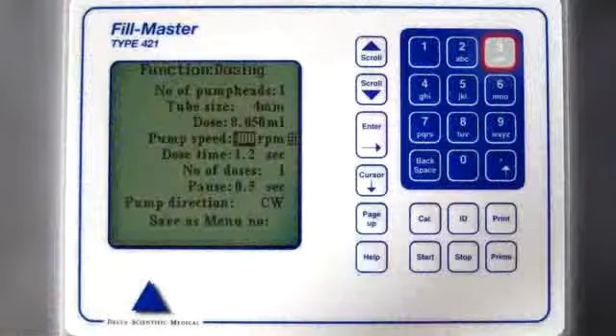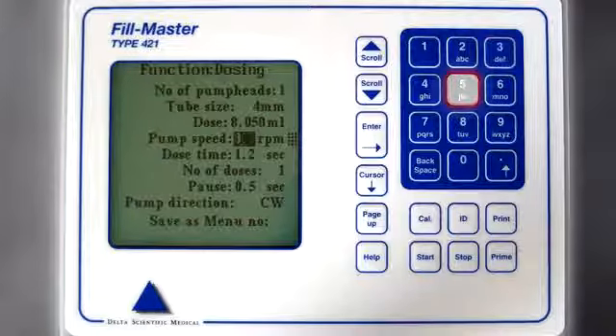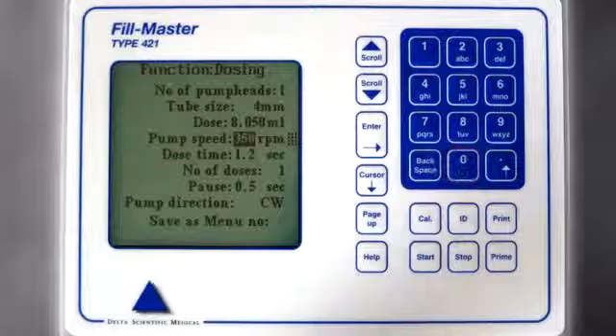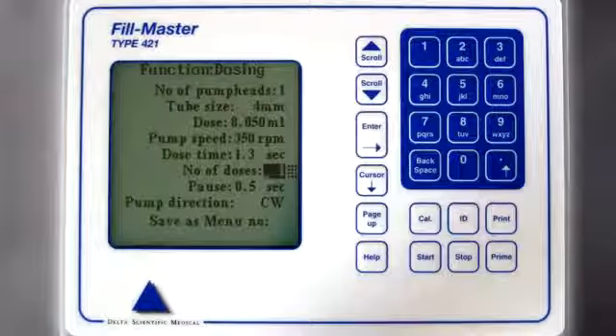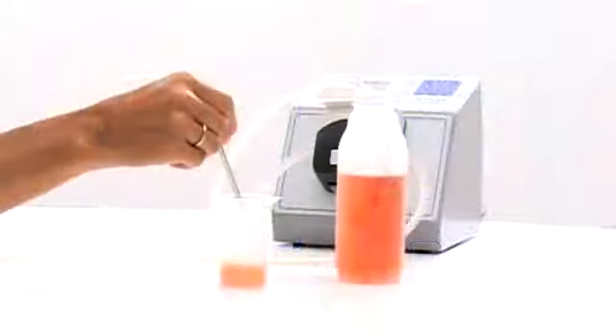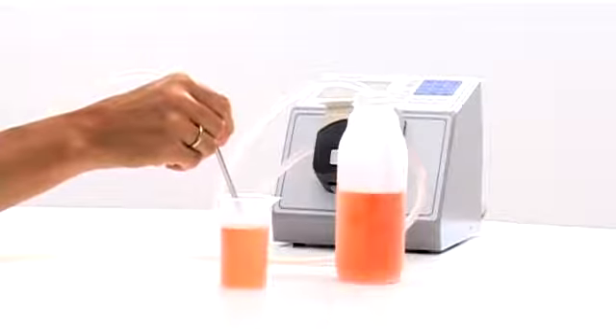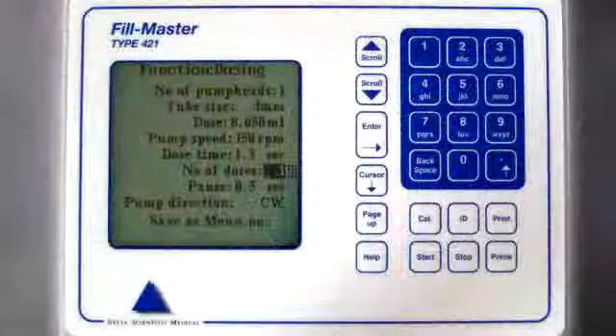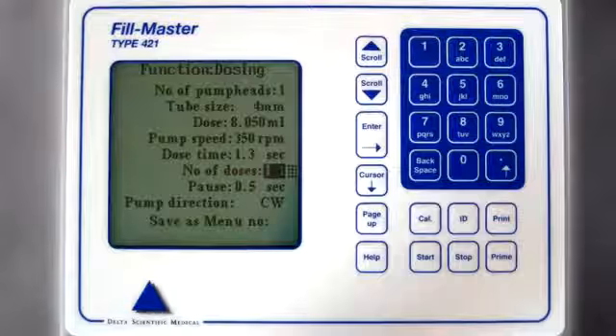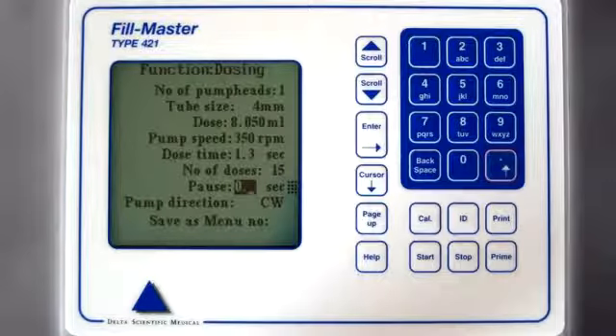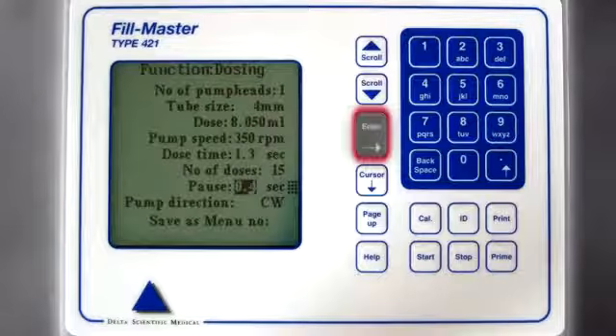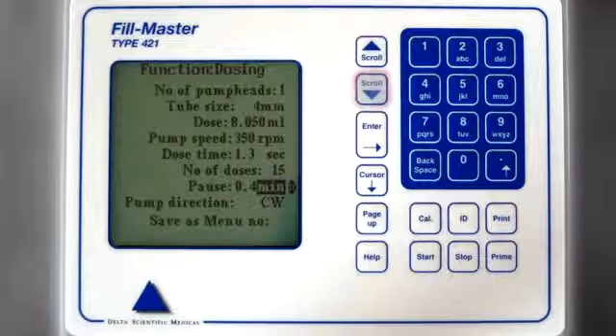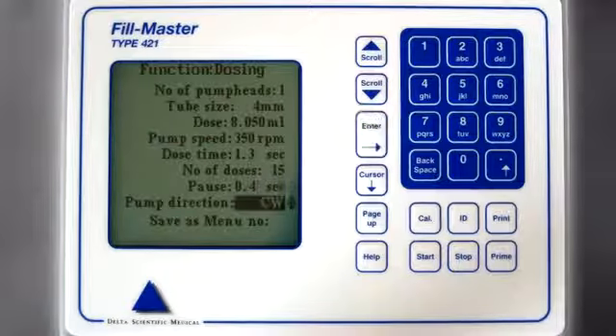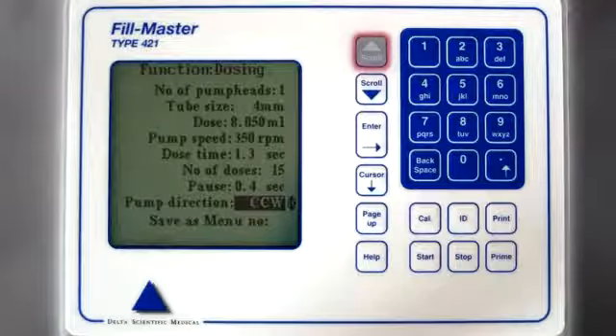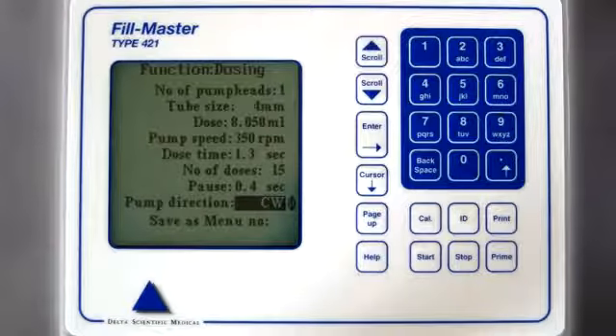In the pump speed line, you can choose speeds from 1 to 500 RPM. Use the keyboard and insert desired speed and press Enter. In the next line, you can now read dose time, telling you how long it takes to dispense the volume you have requested with the tube size and pump speed you have chosen. The cursor has now moved to number of doses, and again, use the keyboard to key in how many you want and press Enter. In pause, insert the pause between fillings using the keyboard. Press Enter. Choose between seconds and minutes using the scroll buttons. Press Enter. In pump direction, use the scroll buttons to choose between clockwise or counterclockwise and press Enter.